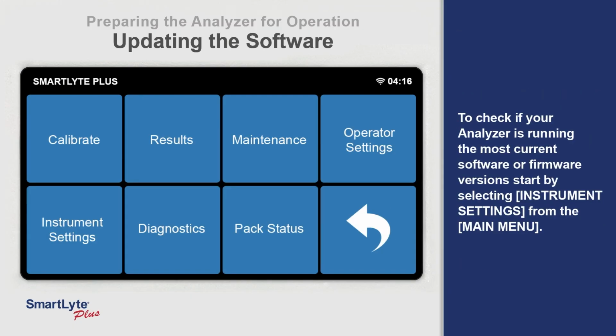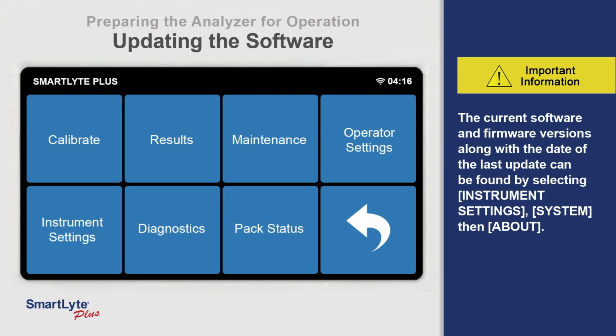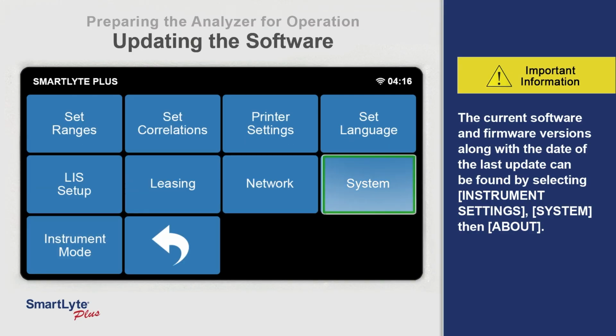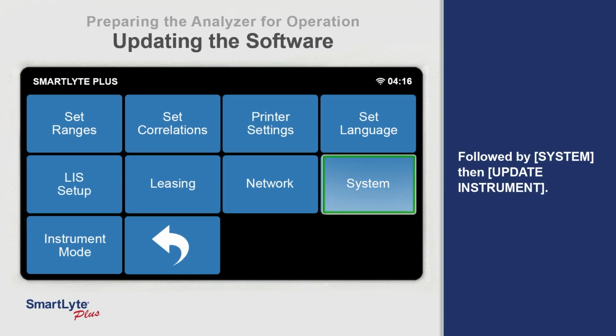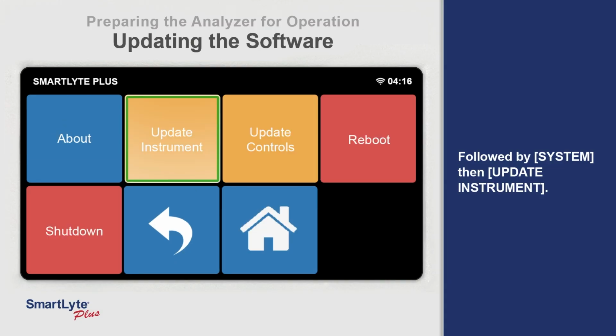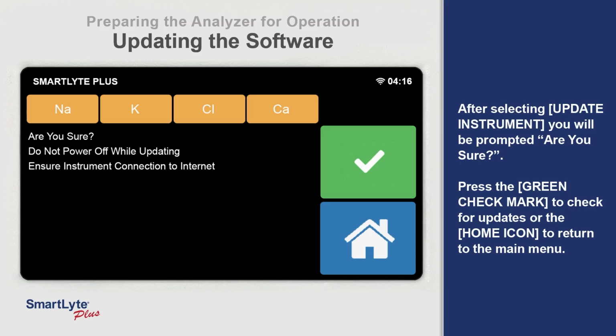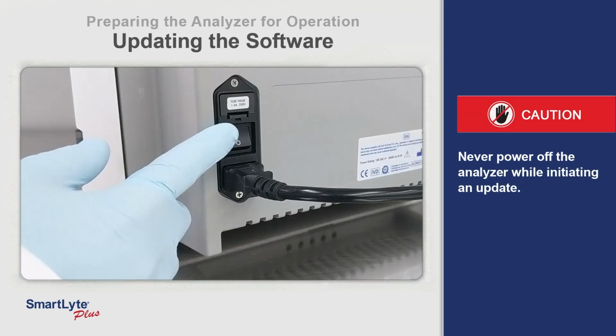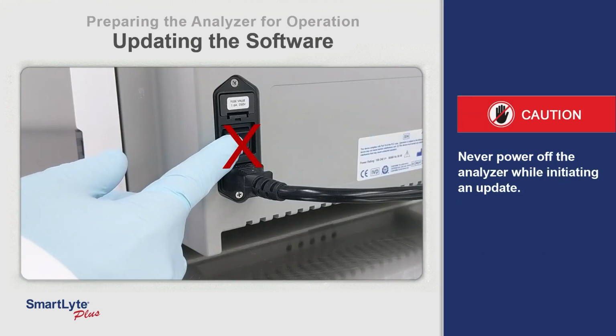To check if your analyzer is running the most current software or firmware versions, start by selecting Instrument Settings from the main menu. The current software and firmware versions, along with the date of the last update, can be found by selecting Instrument Settings, then System, then About, followed by System, then Update Instrument. After selecting Update Instrument, you will be prompted, "Are you sure?" Press the green check mark to check for updates or the home icon to return to the main menu. Never power off the analyzer while initiating an update.